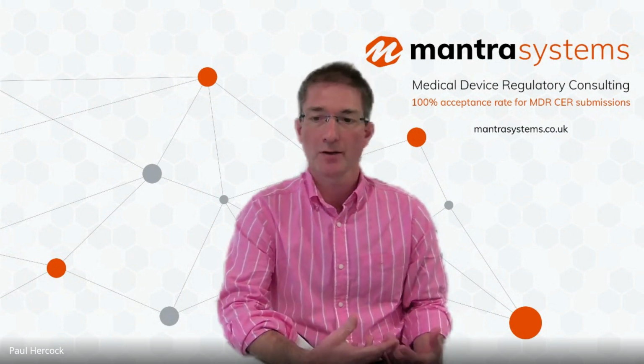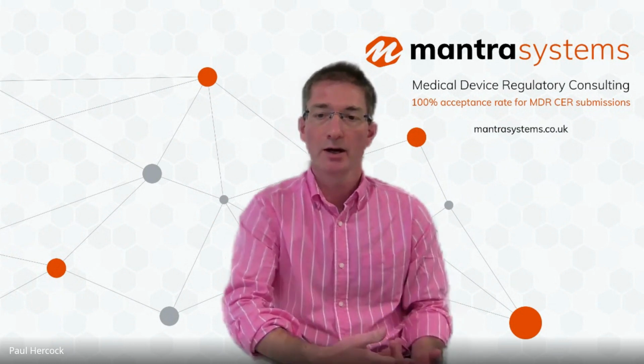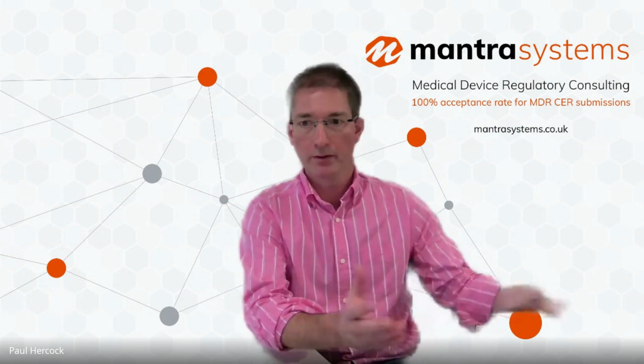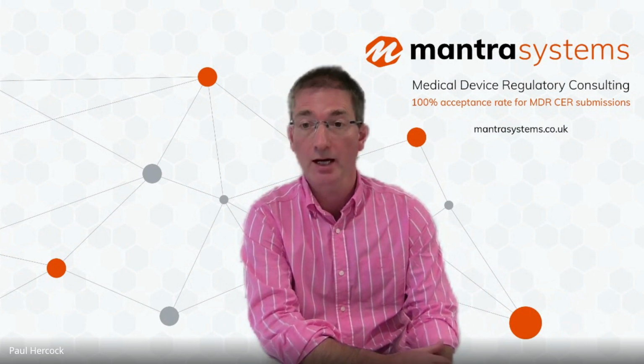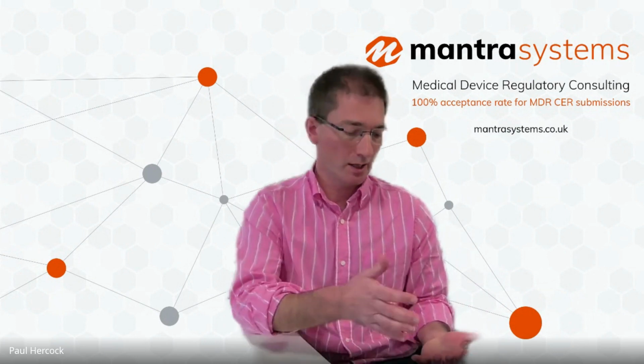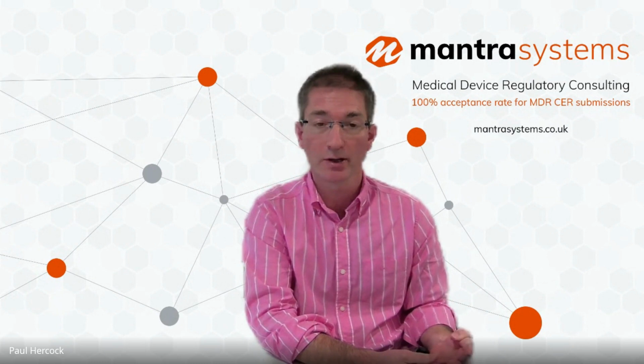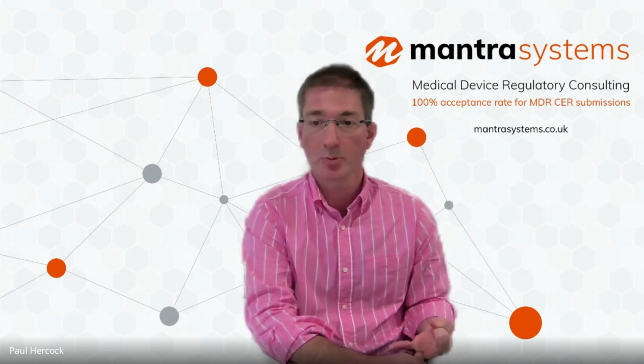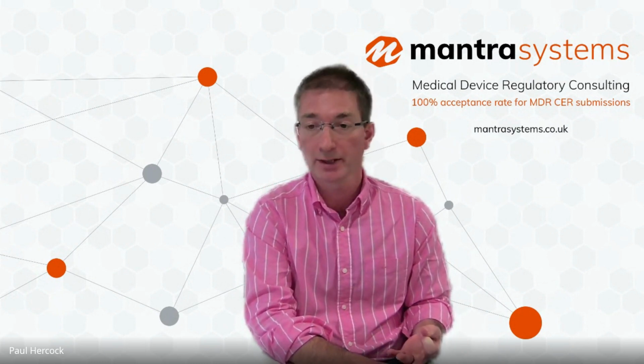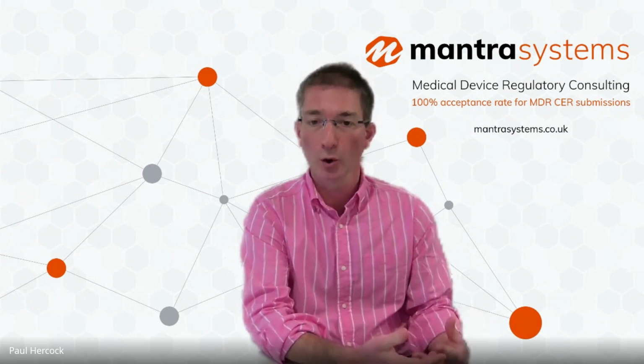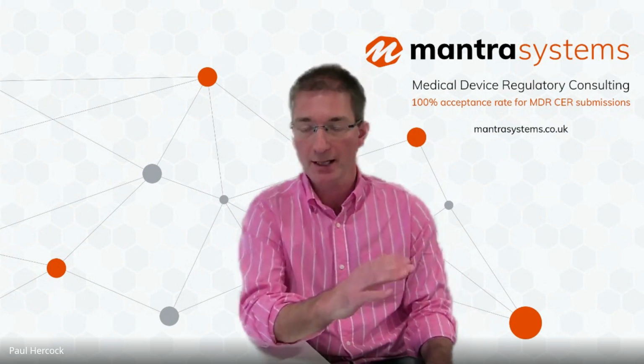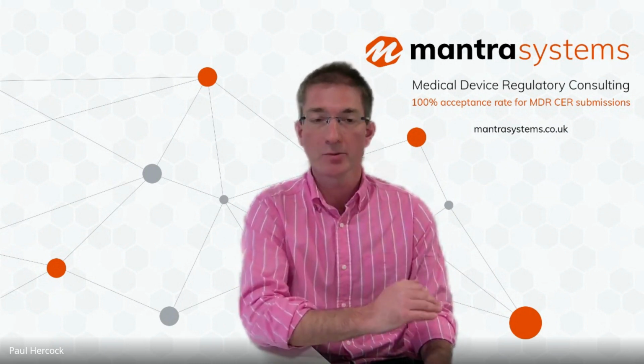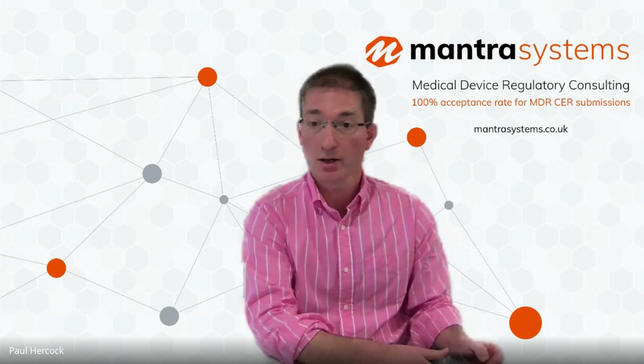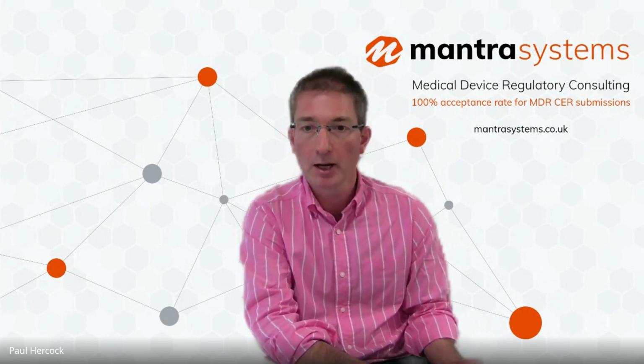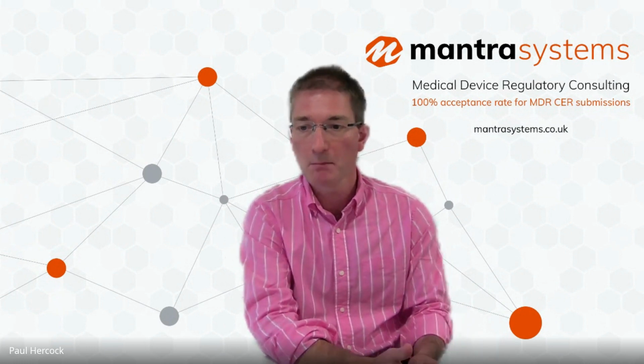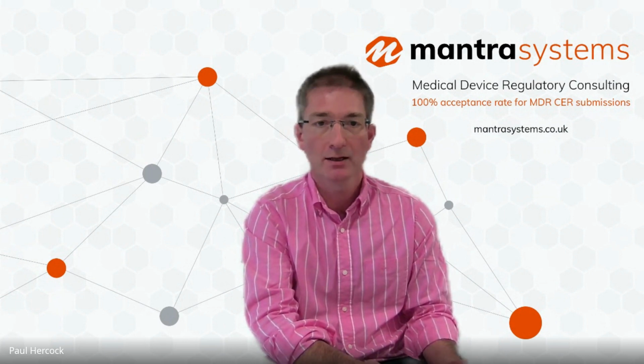Assuming you can demonstrate you have sufficient access to data and you don't need a contract, or that you have a contract, then it's just a case of looking at the three types of characteristics that you need to consider: technical characteristics, biological characteristics, and clinical characteristics. And you need to be equivalent in all of these. And of course, under those headings, there'd be a number of line items depending on the type of device.